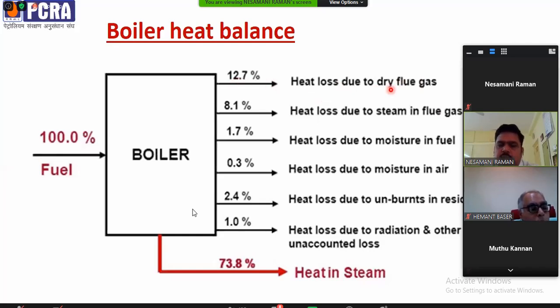It is due to loss due to dry flue gas because of stack temperature. If you keep stack temperatures high, this loss will increase further. The second is heat loss due to steam in flue gas, because the steam in the flue gas will absorb some amount of good heat from the fuel, thereby lowering our efficiency. Almost 8.1% will be lost in the steam due to flue gas.